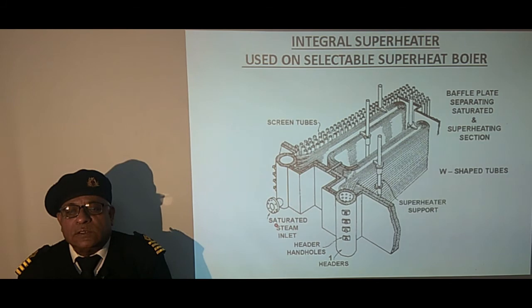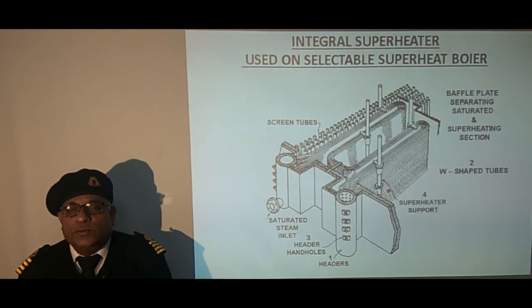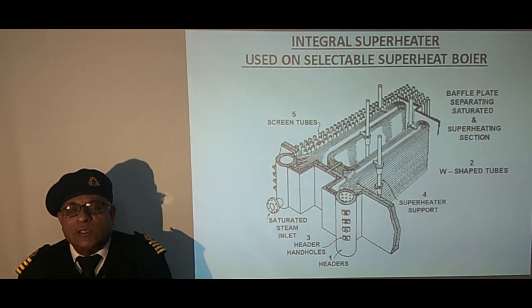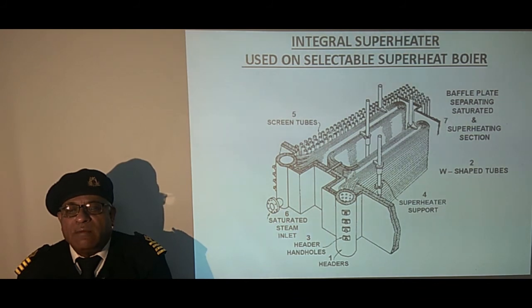Let us see the various components of this superheater. First we have the headers, then the W-shaped tubes attached to the headers. Third are the handholes for getting access to the tube internals. Then we have superheater support tubes taking the weight of the tubes. Then we have three rows of large diameter screen tubes so that the intensity of the furnace cannot reach the superheater. Then we have the saturated steam inlet on one side and the outlet on the other side. We have a division plate dividing the gas flow in two parts — partly over the superheater and partly over the saturated section.